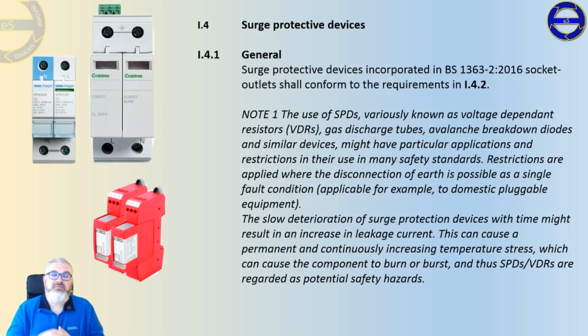It's my kind of a pet hate I have about the lightning protection industry, because in the old days, BS 6651 gave you a really good formula for do I need to do lightning protection. Now the formulas are just basically do it. I've never been on an installation where the minute you do a lightning protection risk assessment, you don't have to buy a rod, a tape and a piece of equipment. So for me, on my domestic installation, I will be doing a risk assessment and a departure where I will document the fact that I don't want surge protection. However, this is the problem.